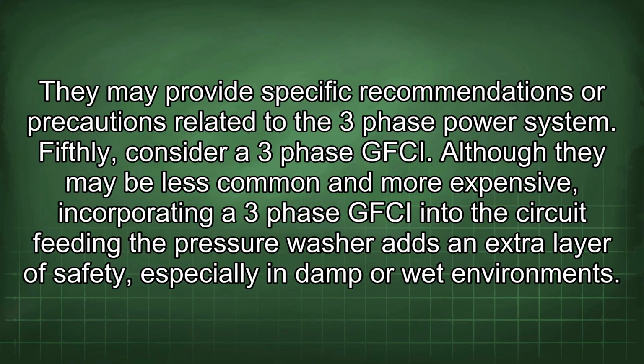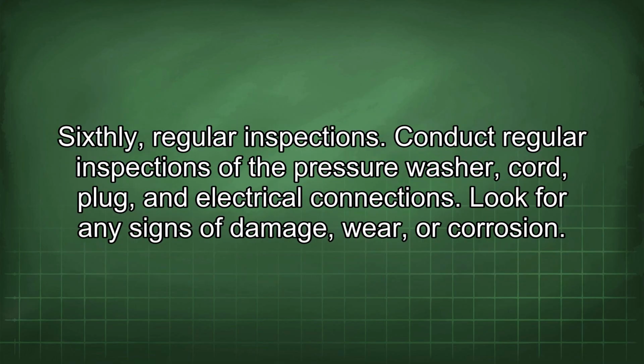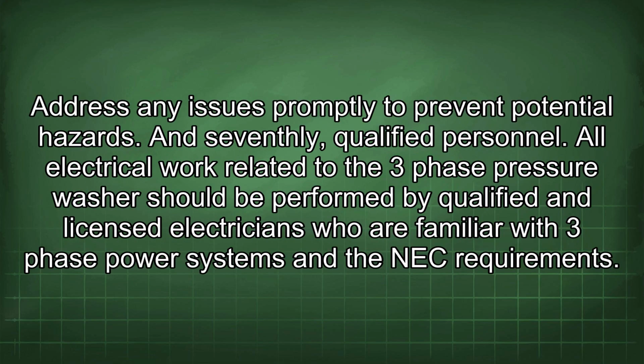Fifthly, consider a three-phase GFCI. Although they may be less common and more expensive, incorporating a three-phase GFCI into the circuit feeding the pressure washer adds an extra layer of safety, especially in damp or wet environments. Sixthly, regular inspections. Conduct regular inspections of the pressure washer, cord, plug, and electrical connections. Look for any signs of damage, wear, or corrosion. Address any issues promptly to prevent potential hazards. And seventhly, qualified personnel.